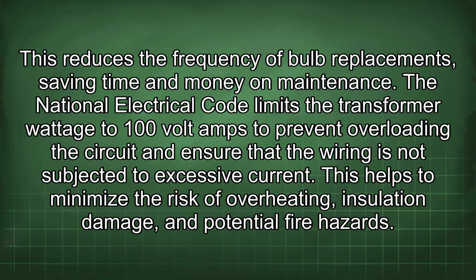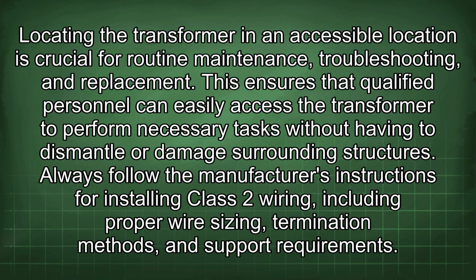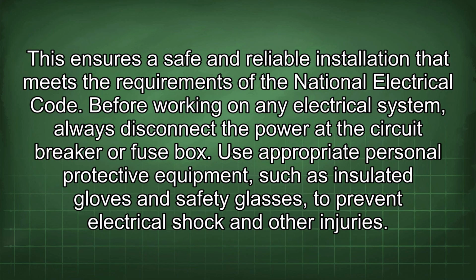The National Electrical Code limits the transformer wattage to 100 volt amps to prevent overloading the circuit and ensure that the wiring is not subjected to excessive current. This helps to minimize the risk of overheating, insulation damage, and potential fire hazards. Locating the transformer in an accessible location is crucial for routine maintenance, troubleshooting, and replacement. This ensures that qualified personnel can easily access the transformer to perform necessary tasks without having to dismantle or damage surrounding structures. Always follow the manufacturer's instructions for installing Class 2 wiring, including proper wire sizing, termination methods, and support requirements. This ensures a safe and reliable installation that meets the requirements of the National Electrical Code.